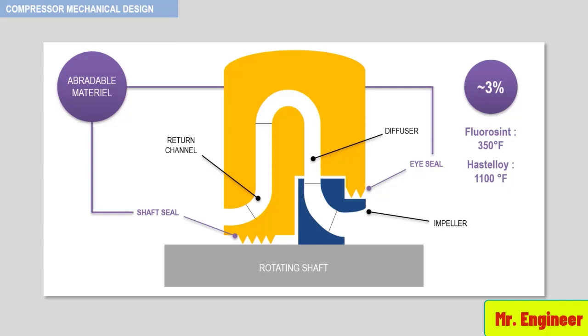Usually, the labyrinth, which looks like knife edges as highlighted here, is positioned on the rotors whenever abradable seals are used. It has proven cost-effective not to attempt to machine knife edges in the abradable material.